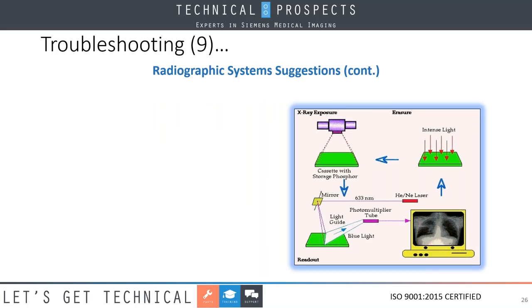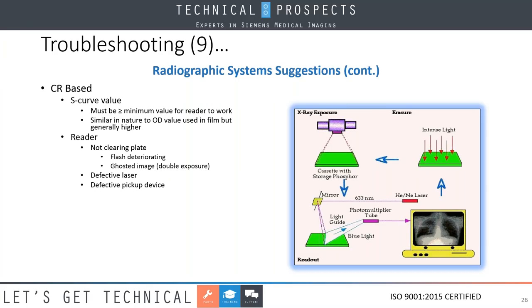When we have a CR type of system, now we're looking at what we call the S curve. Typically this S curve is a value that's needed for the reader, and it's a minimum value for that reader to work. If we're not getting the cassette plate exposed enough, you're not going to get a good quality X-ray. Typically what we found over the years is that with CR systems the S curve is very similar to OD. However, it usually requires a higher level of radiation being given to the patient to get to that particular level. Some problems you may see is the clearing.